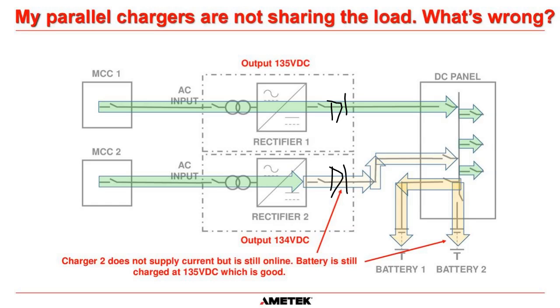Also, what we do with the diode is we have a feedback circuit. So we have to monitor the output of this charger at this point here. And let's say it goes up to 140 volts. We have to monitor that. If we do it before the anode, we know, let's say this charger went up to 140 volts. Well, with this blocking diode here, that wouldn't get back to the anode. If we see 140 volts on this side, we know it's our charger, this one here, that is putting out 140 volts. So our feedback circuit within the charger will say, okay, that's too much. Let's take it back down to 135. So it allows us to control each charger individually. So that's why we have blocking diodes in parallel systems.